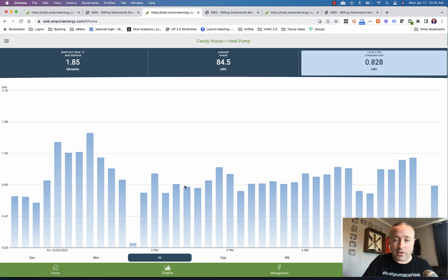I thought that it had changed it, but I made a dumb screw up on this. When you have a 220 device, you only clamp one of the sides of the circuit, but if it shares a neutral, the pull on them is identical. So you take whatever the pull is from one of the circuits and double it, and that's what you get. So you can make your CT clamps go further - you don't need 2 clamps on a 220 device, just 1, then multiply it times 2. Except I didn't multiply it times 2. I left it at 1.